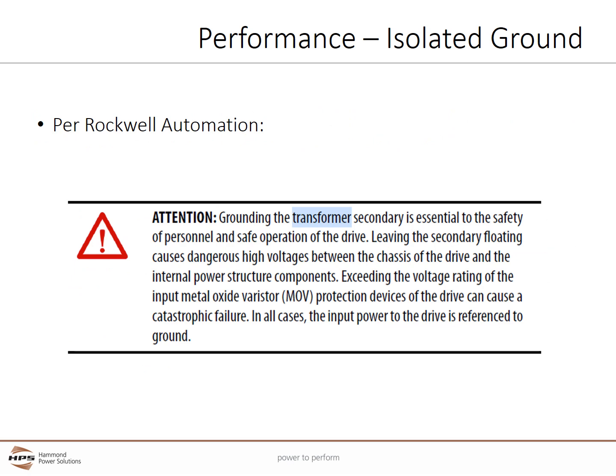While this was taken from a Rockwell Automation manual, other VFD manufacturers have similar warnings. This says that grounding the transformer secondary is essential to the safety of personnel and the safe operation of the VFD. Leaving the secondary floating, and this can be caused unintentionally over time as grounds lose conductivity or are severed, can cause dangerous high voltages between the chassis of the drive and the internal power structure components. Exceeding the voltage rating of the input metal oxide varistor protection devices of your drive can also cause catastrophic failure. In all cases, the input power to the drive should be referenced to ground. This statement provides a powerful incentive to make sure that critical VFDs use a properly grounded system. A DIT offers a dedicated and usually much more local ground to a VFD than a general system can provide.